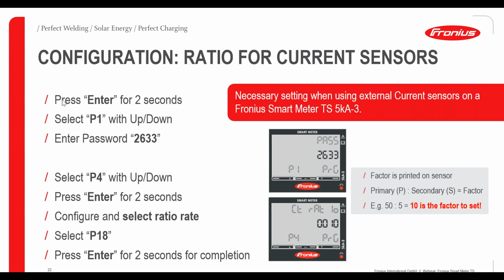And how you do it: again, you press Enter for 2 seconds. You select page 1 here. You enter the same password again. Then you select page 4. After that, you press Enter for 2 seconds. And here you need to enter this factor, which is the factor of 10 in this example. After that, again, you go to page 18 and press Enter for 2 seconds, and you are done with this configuration.